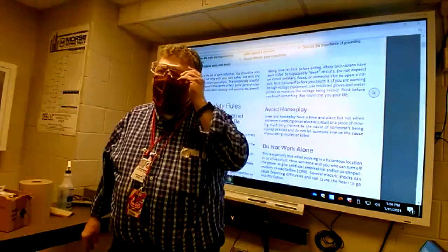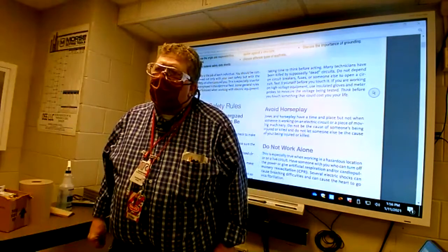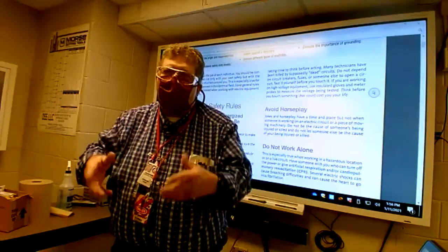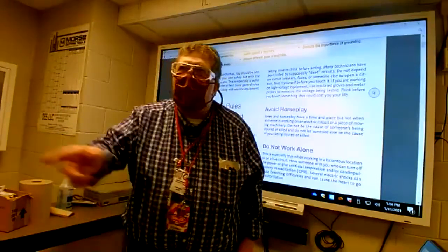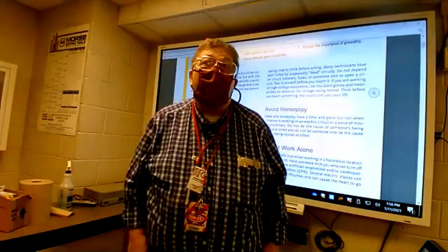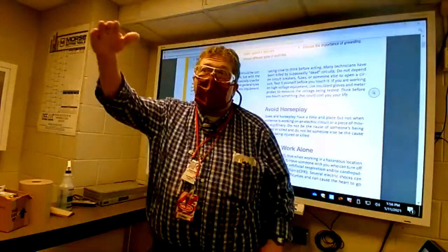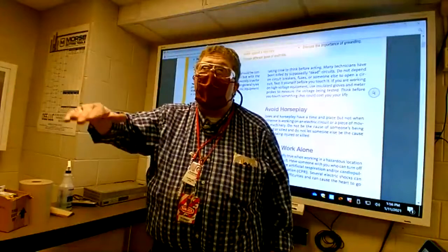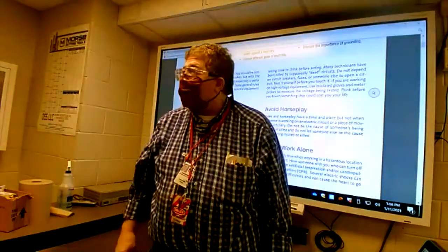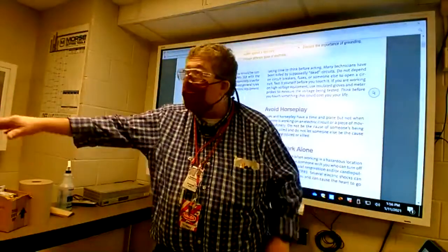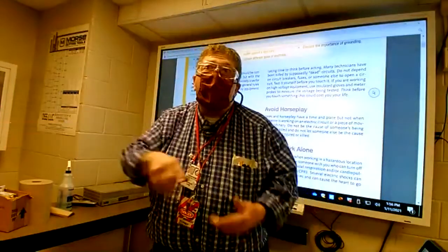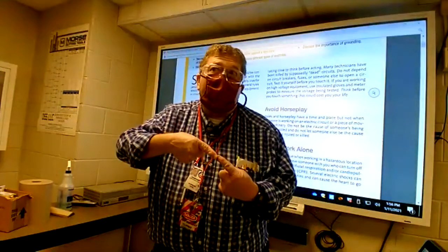Well, I went over there and I said, did you check the power before you went in there? He says, Well, you see that the switch is off. I said, I do see that, but did you use a meter to check downstream of the breaker, leaving the breaker going to where you were? He said, no. He says, you see the switch is off. I said, that doesn't matter. The breaker could be bad. The breaker could be shorted on the inside, welded shut.